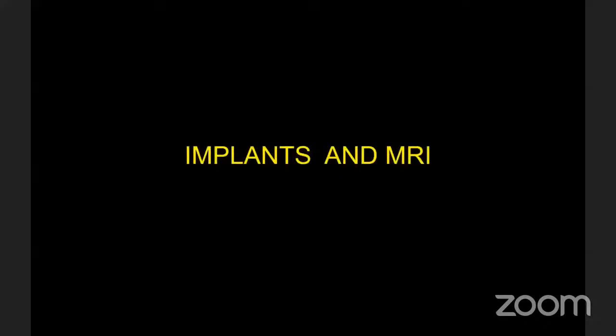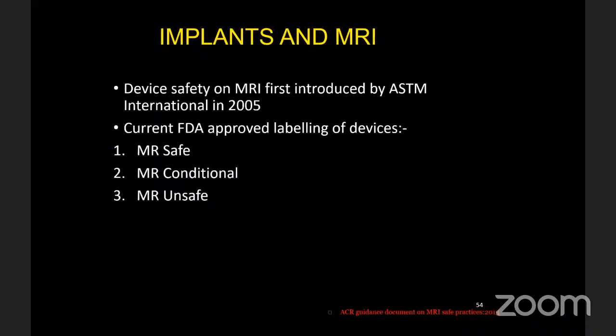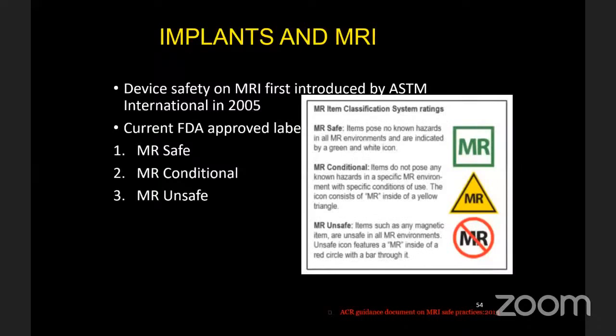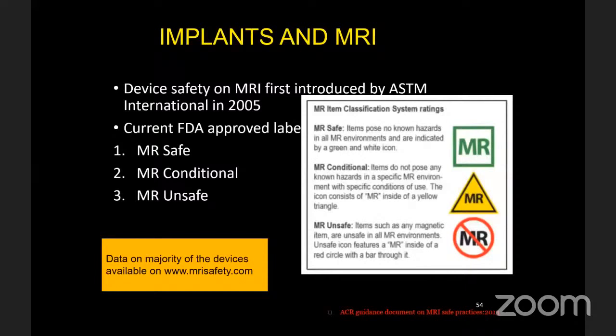Regarding implants and MRI: device safety in MRI was first introduced by ASTM International in 2005. Three categories are defined: MR safe, MR conditional, and MR unsafe. Data on most devices is available at www.mrisafety.com. If the device is MR safe, proceed without issue. If MR conditional, follow specific conditions of use. If MR unsafe, it cannot be used. These categories are color-coded: green for MR safe, yellow for MR conditional, and red for MR unsafe.